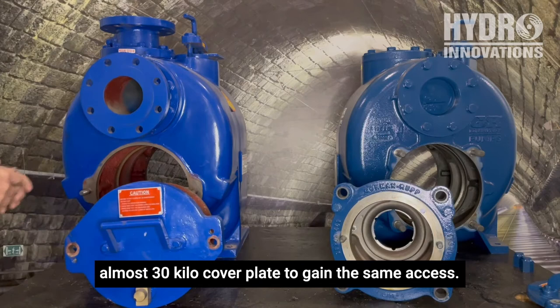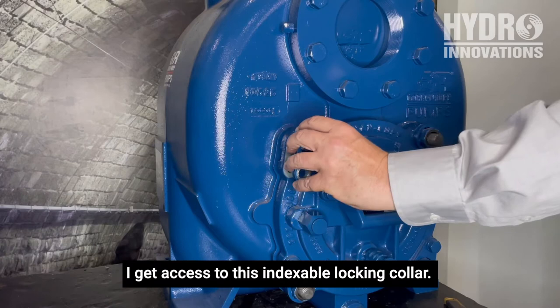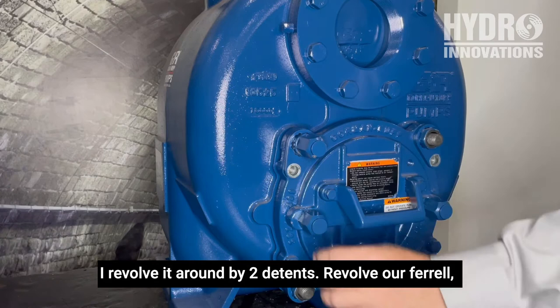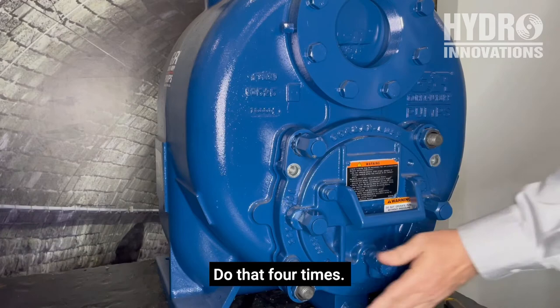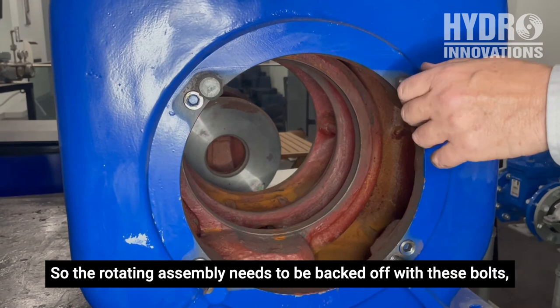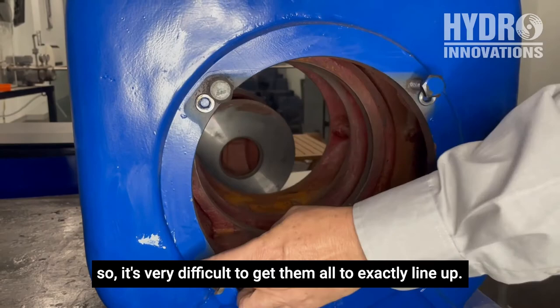Internal clearances wear on a wastewater pump. That's why Gorman-Rupp came up with this clearance adjustment system. By removing the locking collar, I get access to this indexable locking collar — I revolve it around by two detents, then relocate the locking screw. Do that four times and internal clearances have been adjusted by ten thousandths of an inch. Our competitor uses a clearance adjustment system at the rotating assembly side of the pump, where the rotating assembly needs to be backed off with bolts, popped out, and the clearance adjusted with grub screws. There's no indexing, so it's very difficult to get them all to exactly line up.